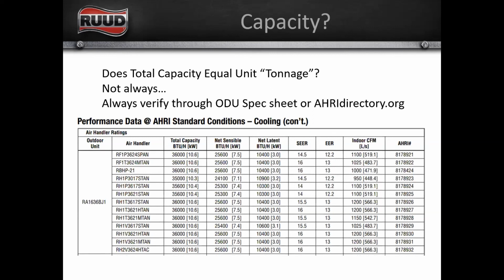And then finally, total capacity does not equal unit tonnage, right? Especially with newer and more modern equipment. So again, we're looking at RA 1636. Depending on what indoor equipment it's matched with, it has a total capacity rating, right? And these are 3 tons, 36,000 BTUs. Matched again with that RH1P, our rated capacity is a little bit less, 35,000 BTUs.